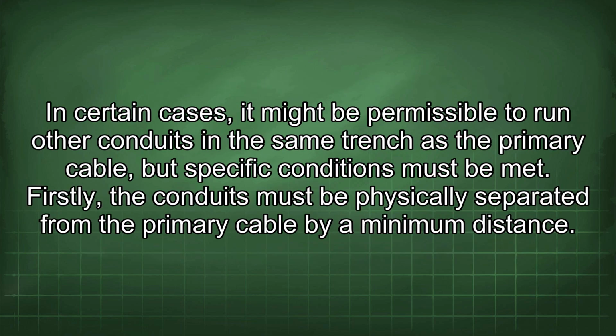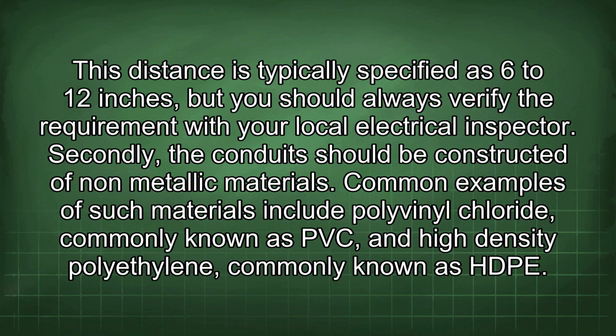In certain cases, it might be permissible to run other conduits in the same trench as the primary cable, but specific conditions must be met. Firstly, the conduits must be physically separated from the primary cable by a minimum distance. This distance is typically specified as 6 to 12 inches, but you should always verify the requirement with your local electrical inspector. Secondly, the conduit should be constructed of non-metallic materials.